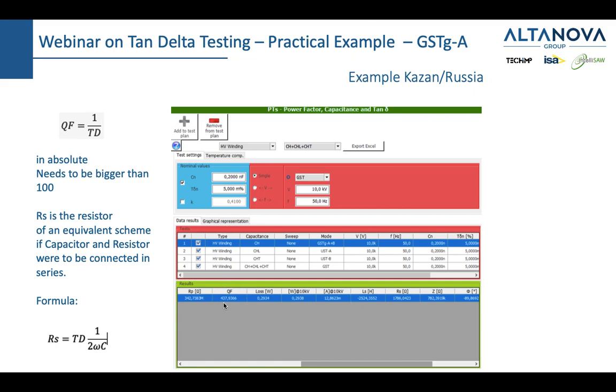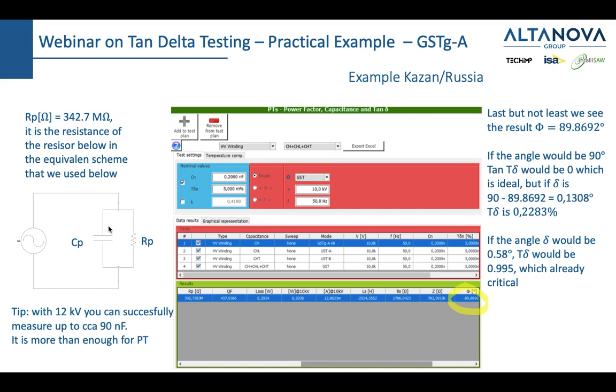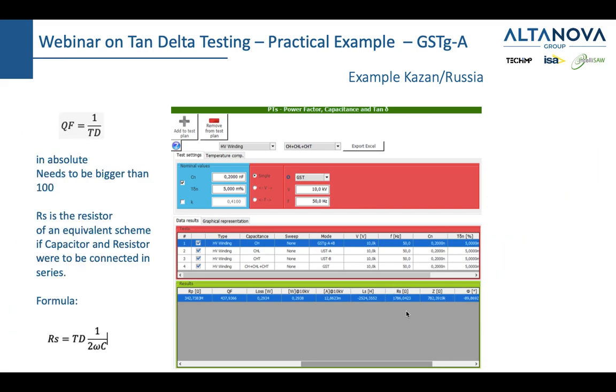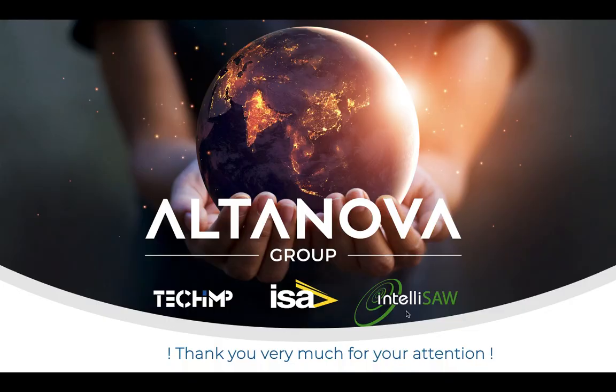QF is nothing but a reciprocal value of a tan delta in absolute terms, so not multiplied by 100, and this number needs to be bigger than 100. If it's smaller, then the tan delta is bigger than 1%. And here we also have RS. RS can also be calculated as tan delta divided by 2 omega C, which actually tells us that if you have an equivalent scheme, which is not the connection of capacitance and resistance in parallel, but capacitance and resistance in series, this is what would be the resistance connected in series. And with this, we close the presentation.